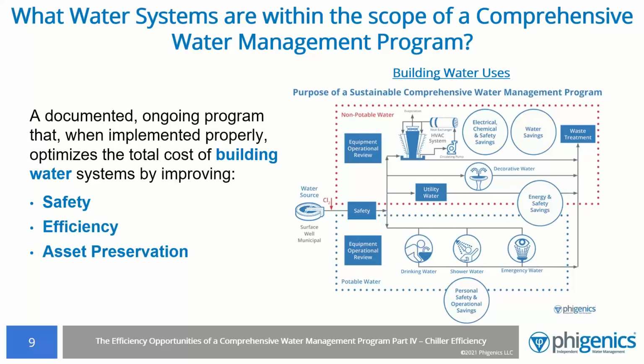A comprehensive water management program is a documented, ongoing program that, when implemented properly, optimizes the total cost of building water systems by improving safety, efficiency, and asset preservation. It includes all of the different potable and non-potable uses of water in a building. We start with ASHRAE Standard 188, which is a water safety standard, and then we adapted the hazard analysis process within the ASHRAE standard to help identify efficiency opportunities.